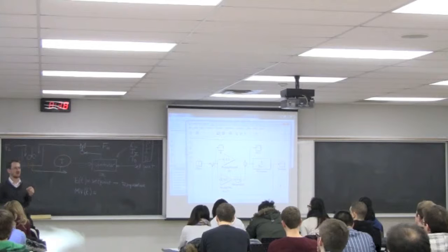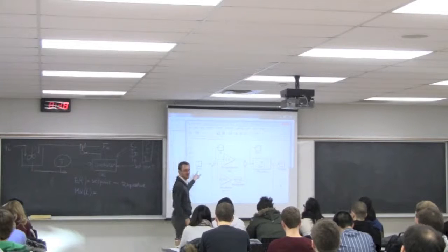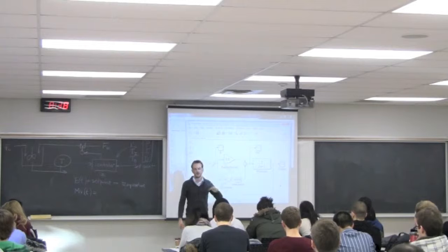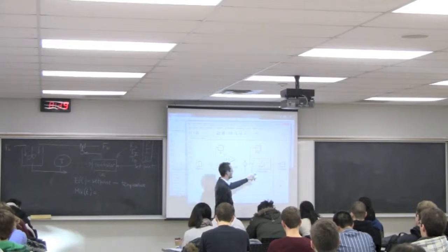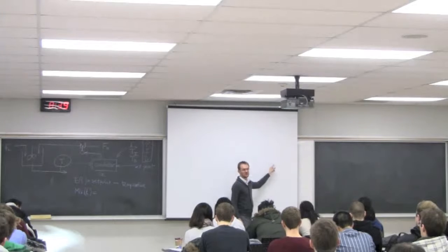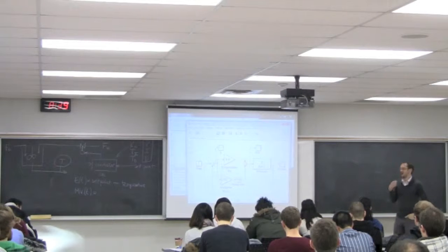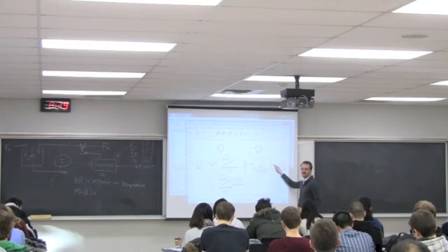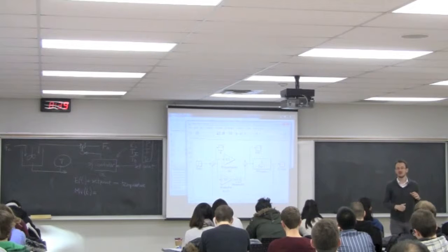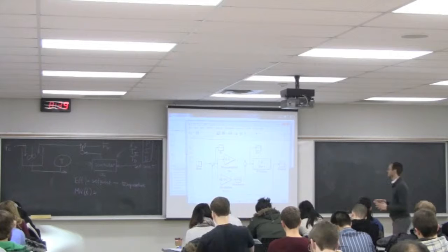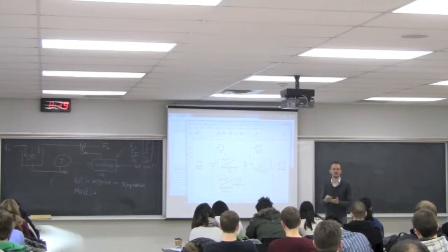Another simplification I've made is to assume that control happens on a continuous basis — that these signals cycle around continuously. But in practice we have digital control systems. The digital control system samples maybe once per second or once every five seconds. The digital controller operates on a set cycle: it measures the sensor value, waits a couple of seconds, measures again, and sends the signal back. The behavior of the process isn't much different assuming continuous versus discrete operation.